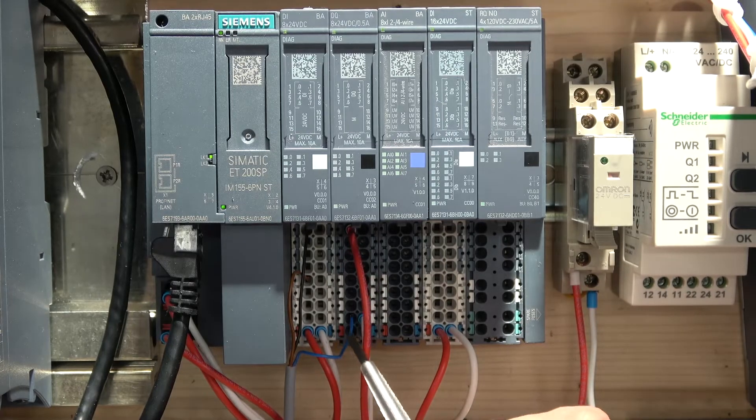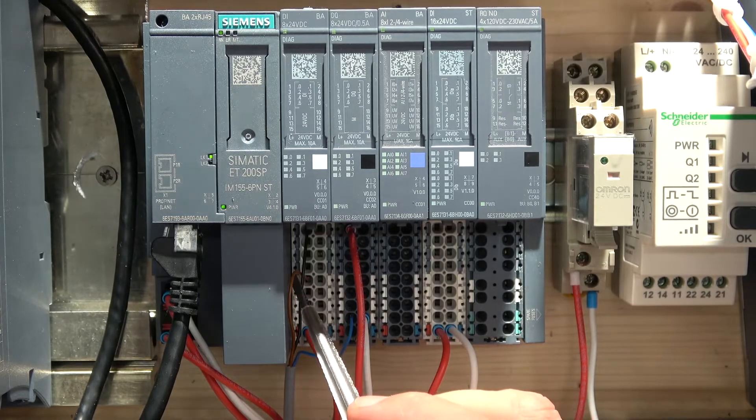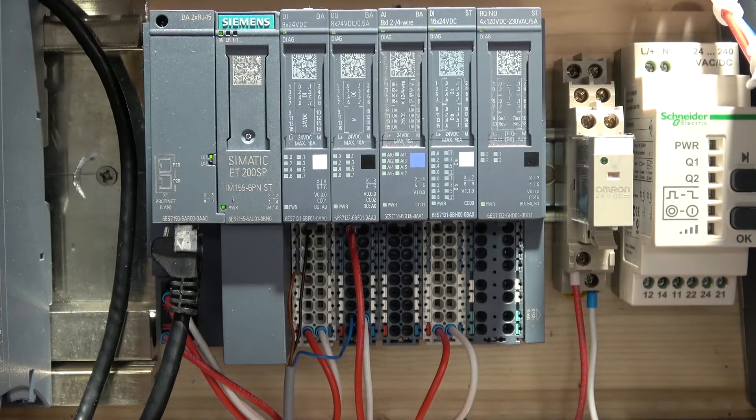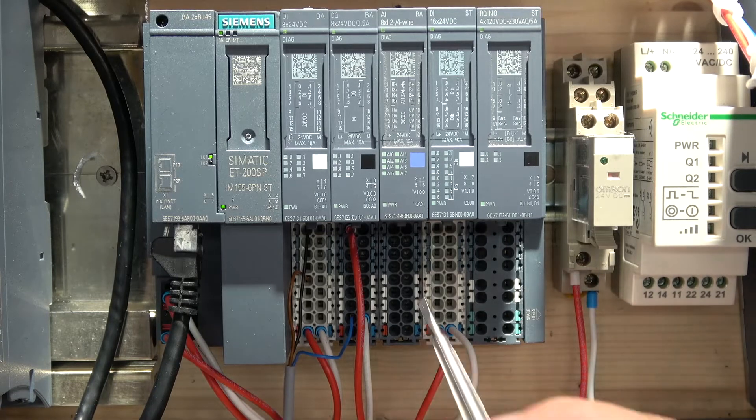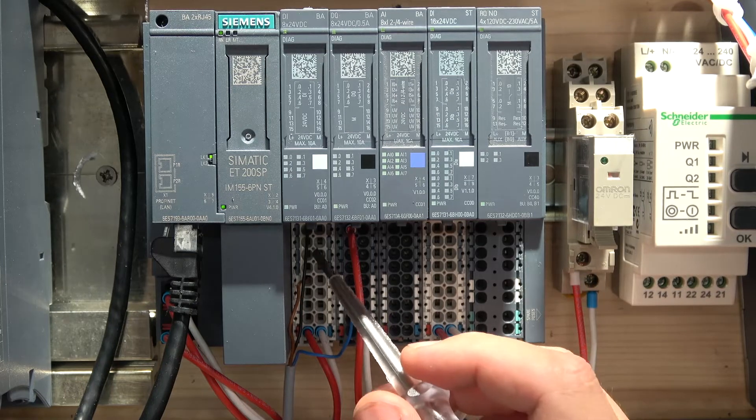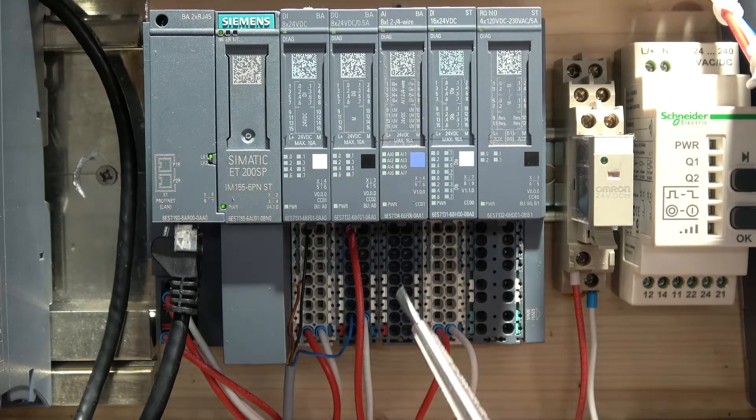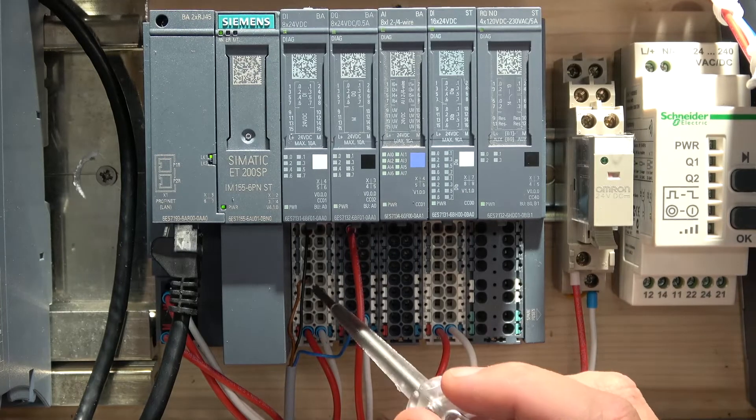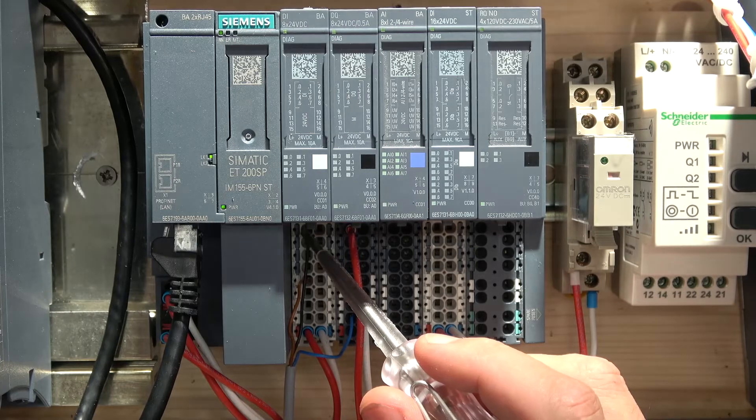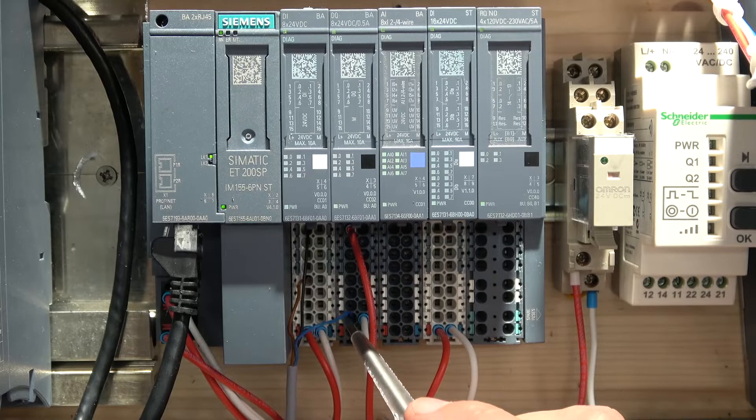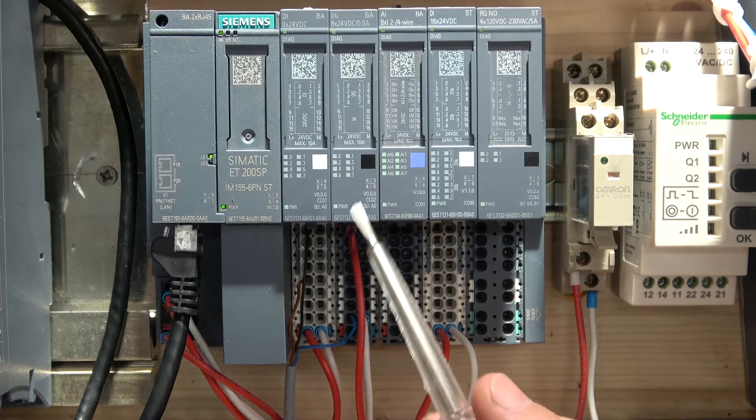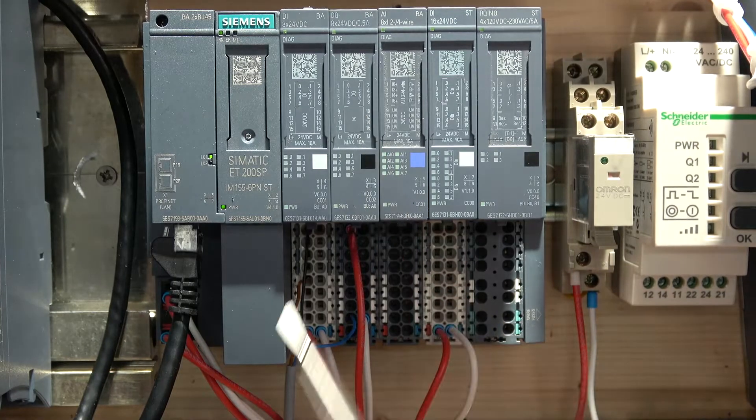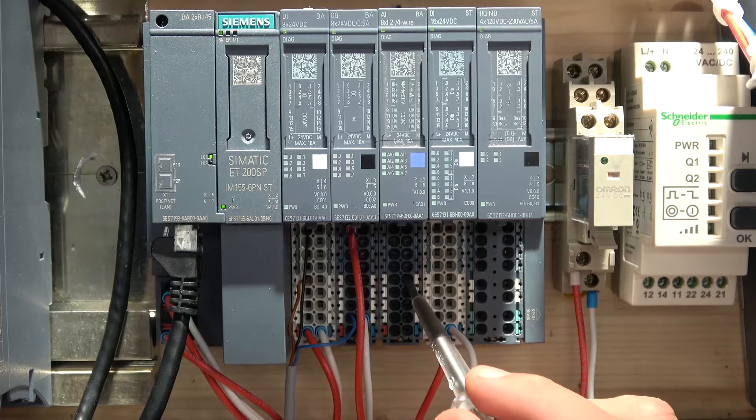Induction sensors or proximity sensors usually come with blue, brown, and black colors. Blue is negative, brown is positive, and black is usually the switching wire that sends back 24 volt DC supply which this brown one is supplying. This is PNP. So 24 volts goes away, comes back, and activates my input. As you can see, I'm actually taking this negative from my output card because I'm allowed to do it because it's M, the negative of this power supply which powers these three cards.